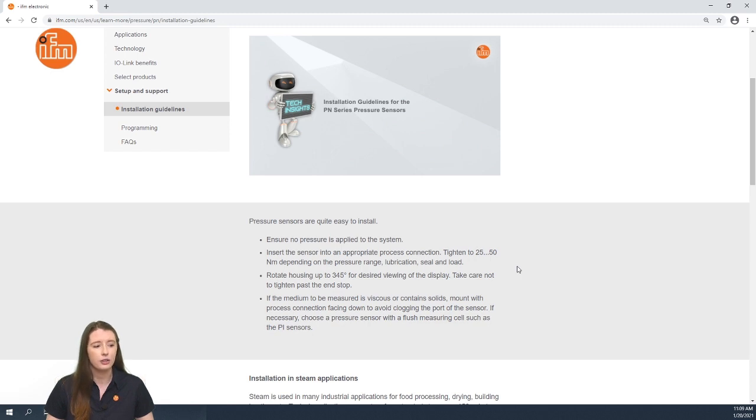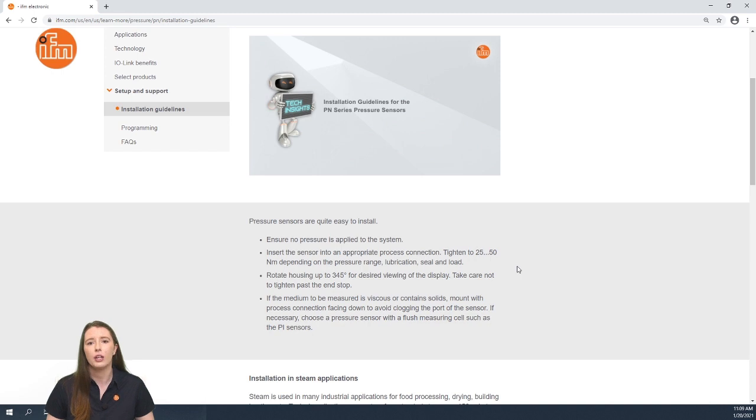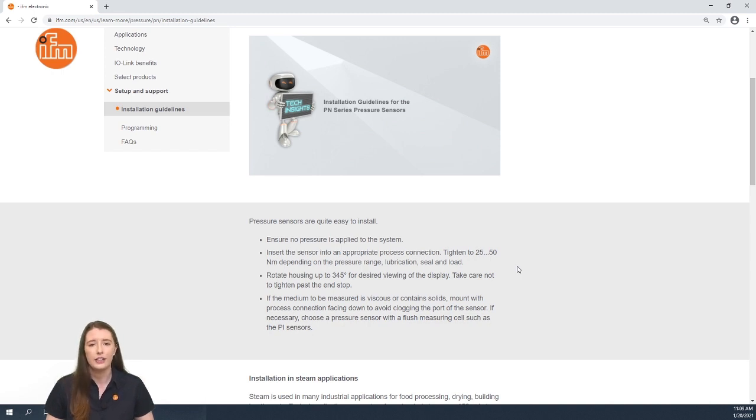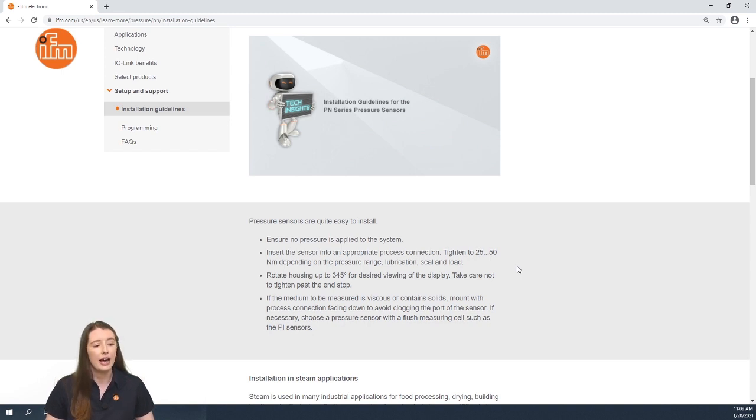And finally, if the media being measured is viscous or contains solids, you want to have the process connection facing downward to avoid clogging. If this is not possible, we do offer our PI series pressure sensors that have a flush measuring cell.